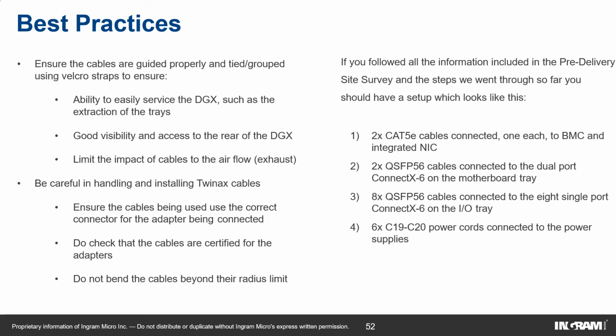If you have followed all the information in the pre-delivery site survey forms and the steps we went through so far, you should have a setup like this: at least 2 Cat5 cables connected, one each to BMC and the integrated NIC; 2 QSFP56 cables connected to the dual port ConnectX-6 on the motherboard tray; 8 QSFP56 cables connected to the 8 single port ConnectX-6 on the IO tray; and 6 power supply power cords, the C19/C20 power cords, connected to the power supplies.